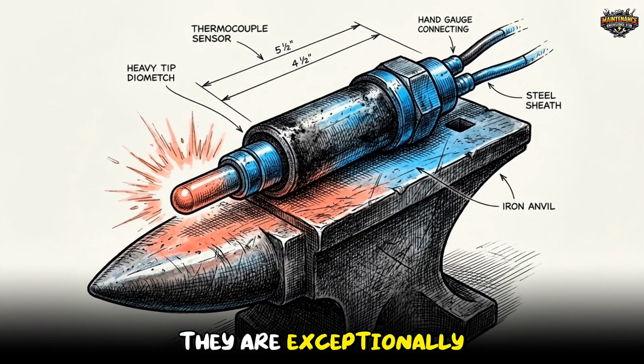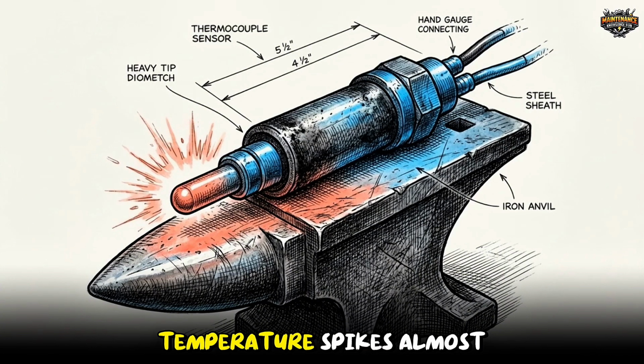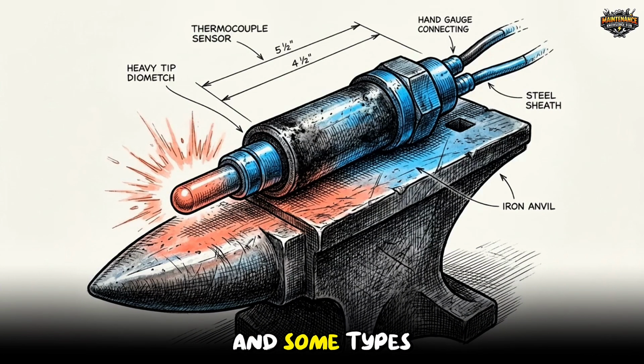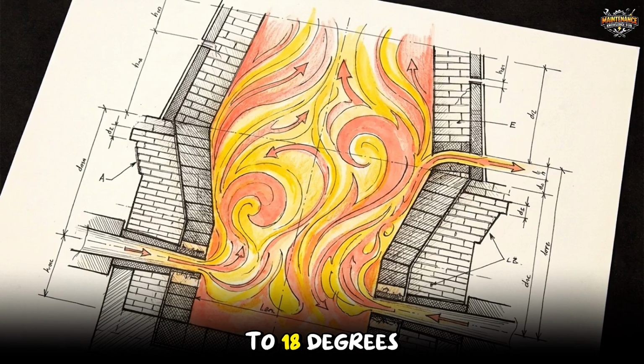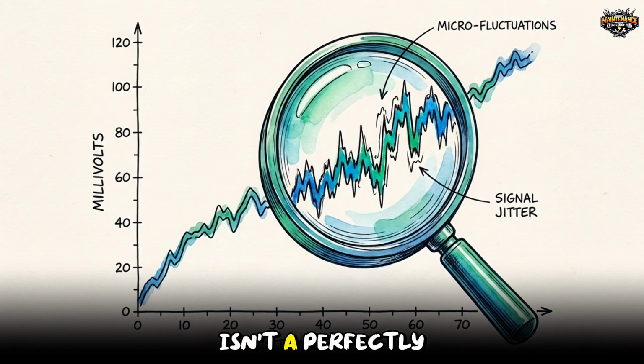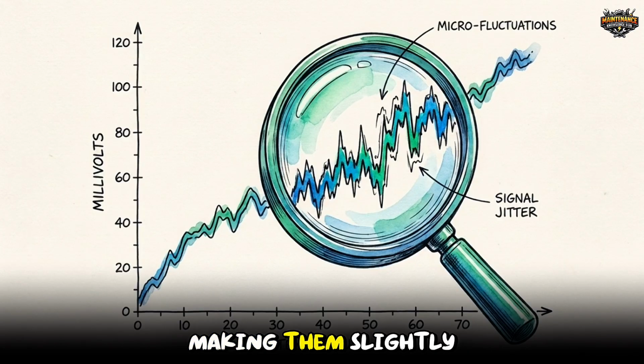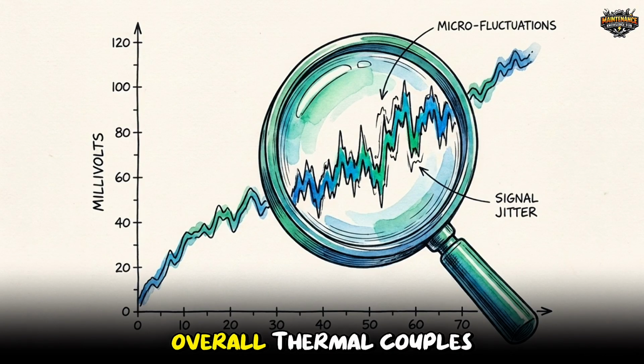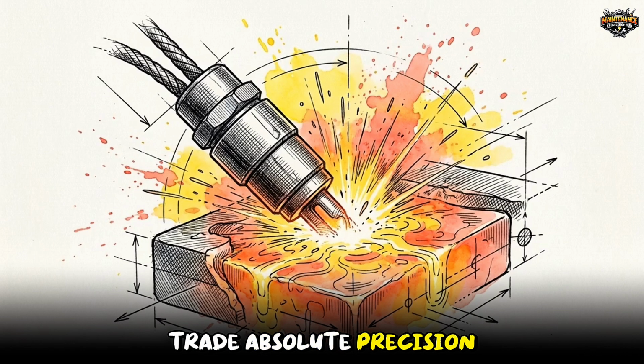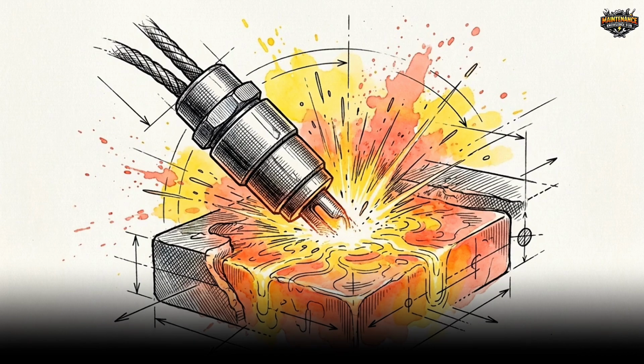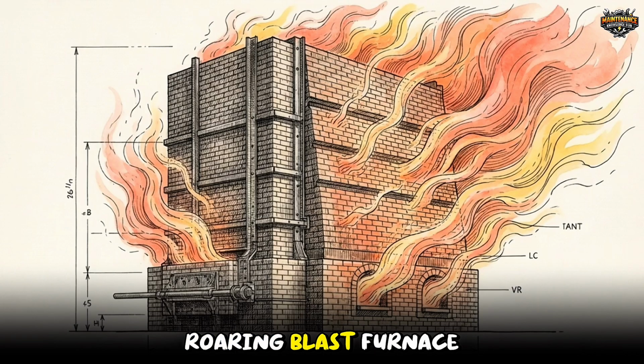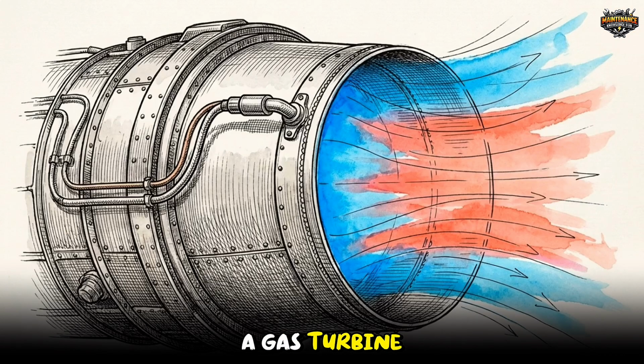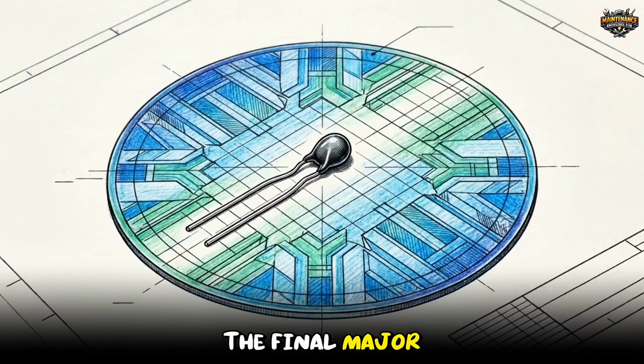They are exceptionally rugged. They react to temperature spikes almost instantly, and some types can survive up to 1,800 degrees Celsius. The trade-off is that their voltage output isn't a perfectly straight line, making them slightly less accurate overall. Thermocouples trade absolute precision for ultimate survivability. If you need to monitor a roaring blast furnace, a kiln, or a gas turbine exhaust, they are the only tools for the job. The final major sensor type moves away from pure metals entirely.